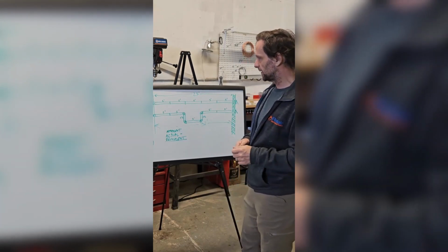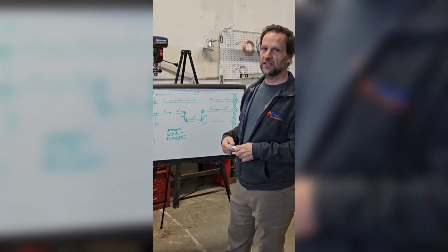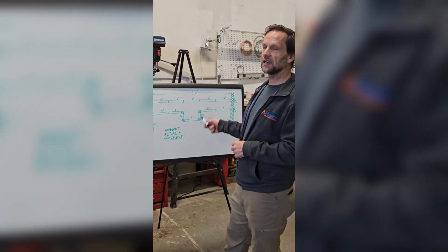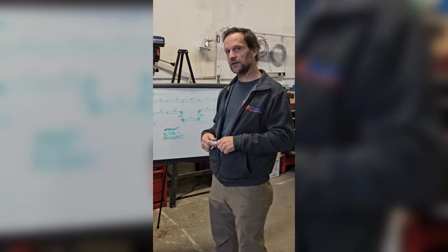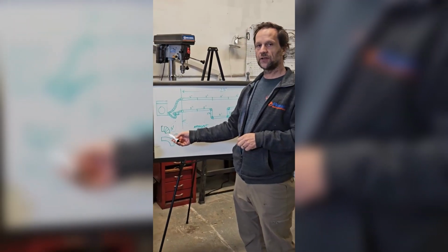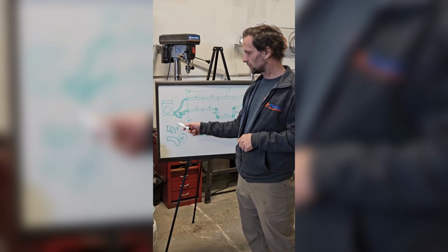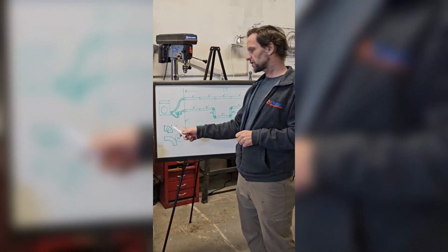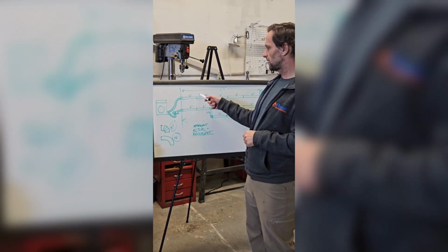What does that mean? You have to take into consideration all the additional resistance that will be created inside the system. One of the greatest contributors to it is that short radius sectional elbow that we saw earlier. That little elbow creates as much friction as 5 feet of straight duct.